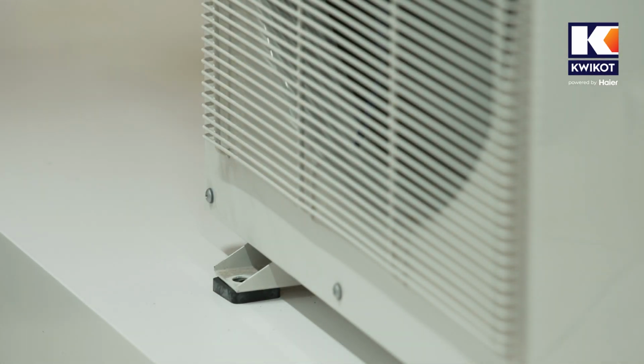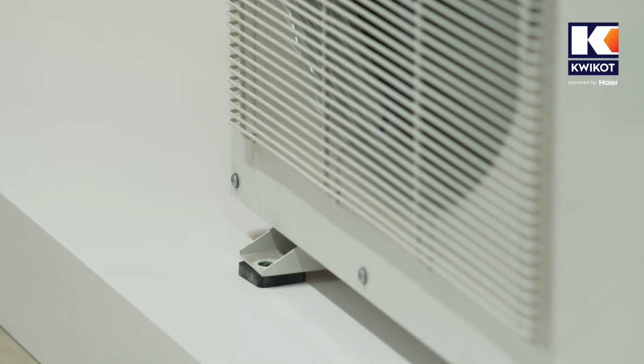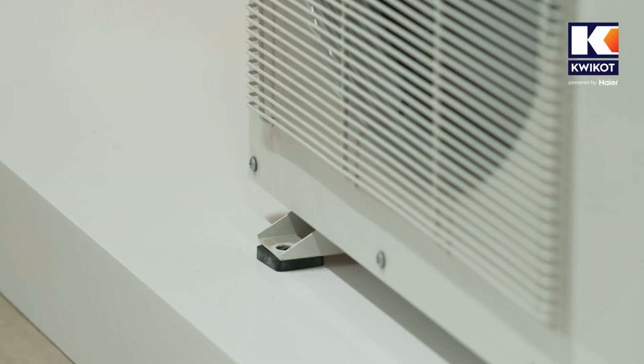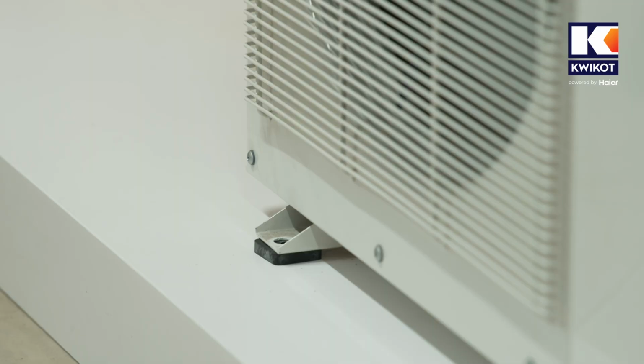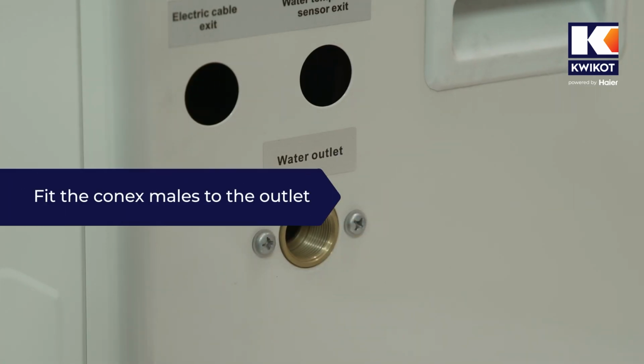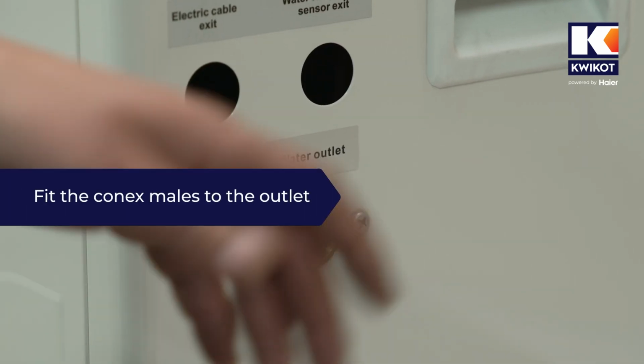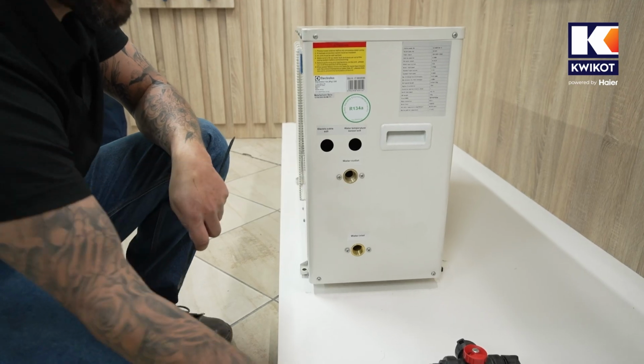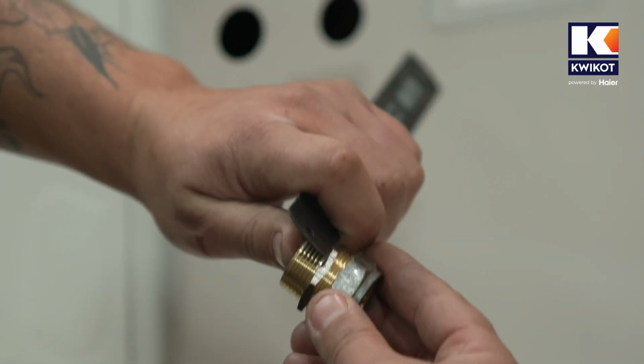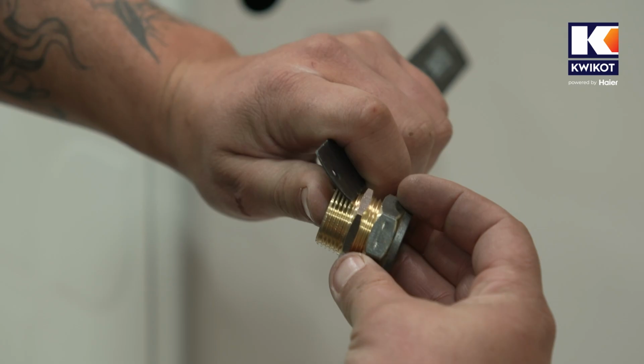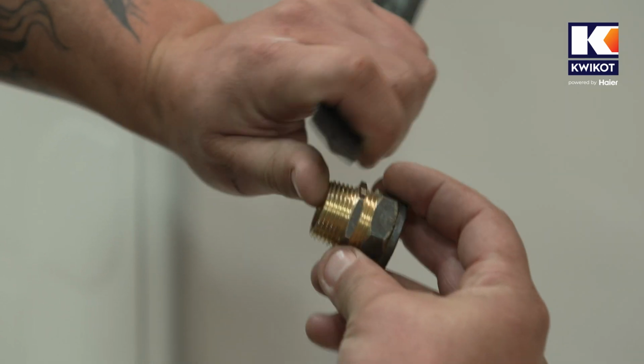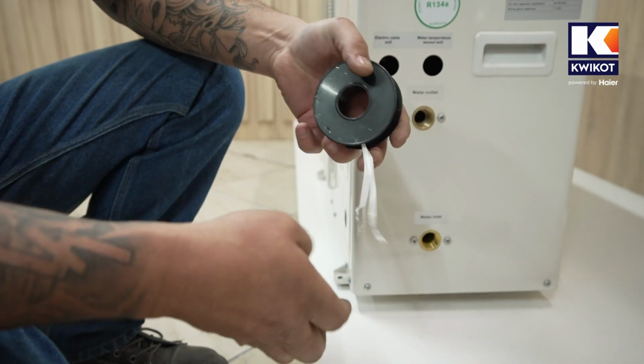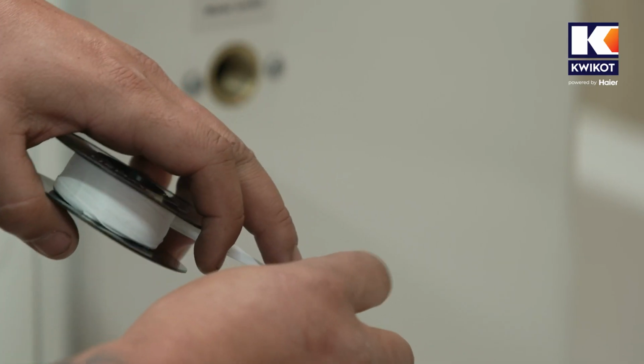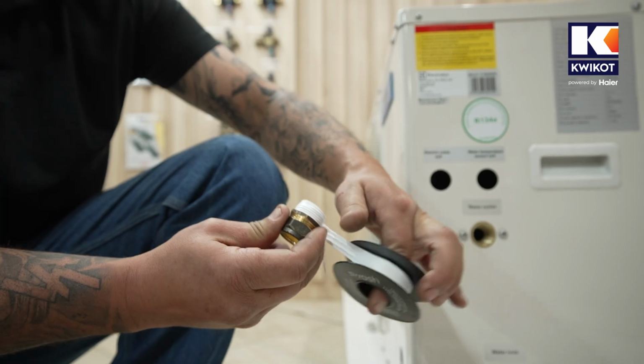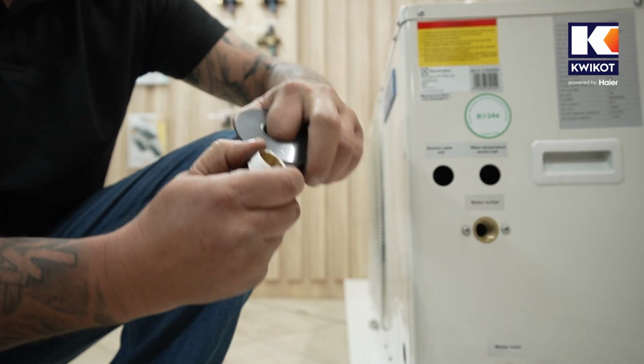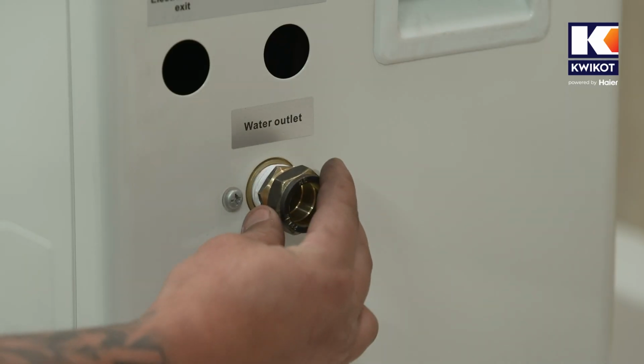The heat pump feet will need to be secured to the surface that the pump is sited on, or alternatively to the brackets supplied if it is wall mounted. Next we will remove the plastic caps from the water outlet and water inlet sockets. And then we take our Connex males and scratch the thread a little. And now you'll take your PTFE tape or hemp and wind it around the thread and insert the Connex into the outlet.